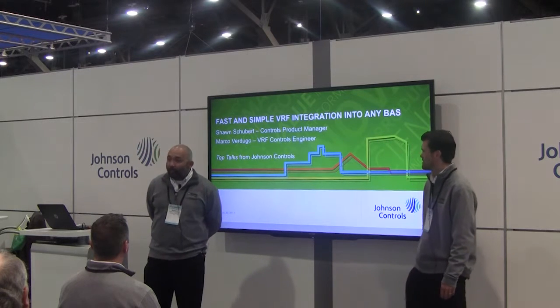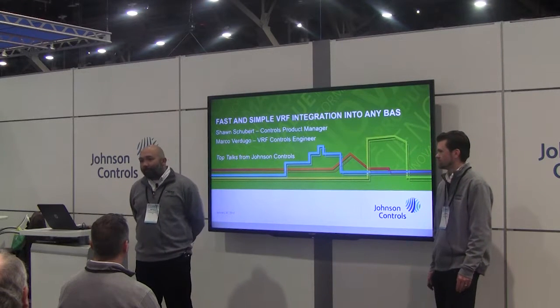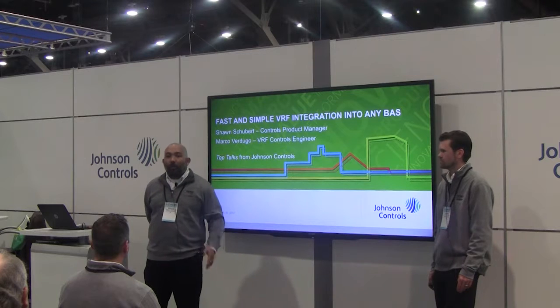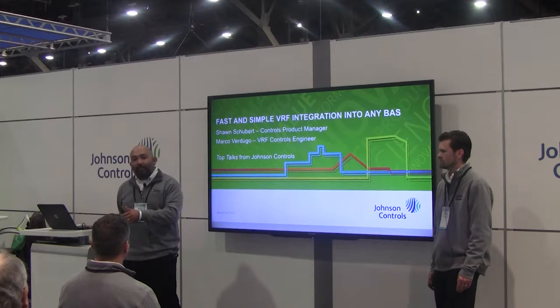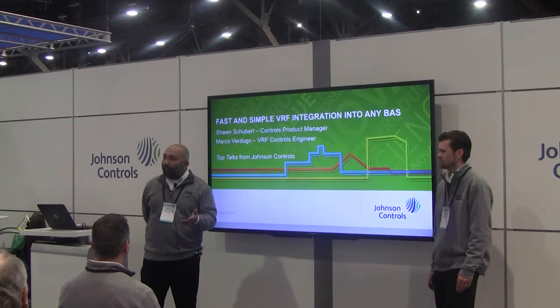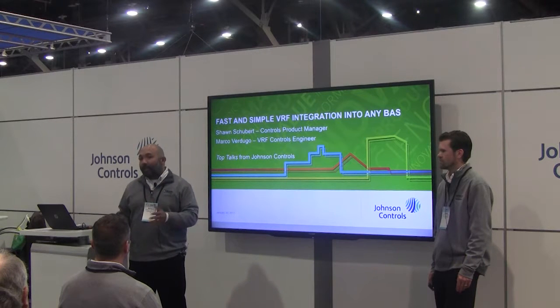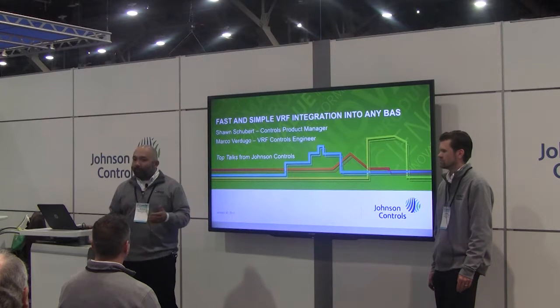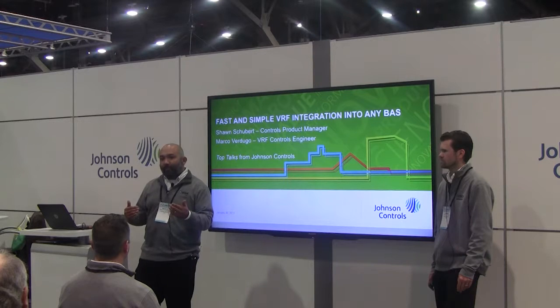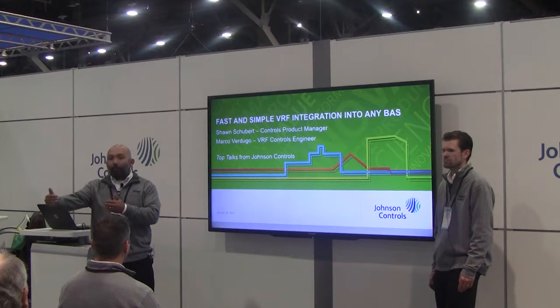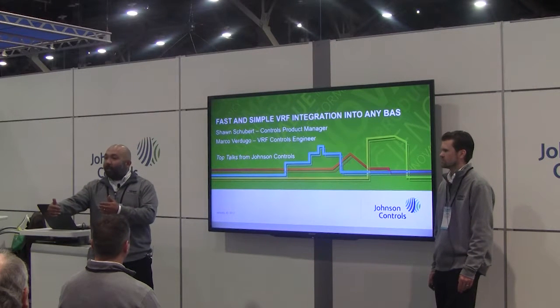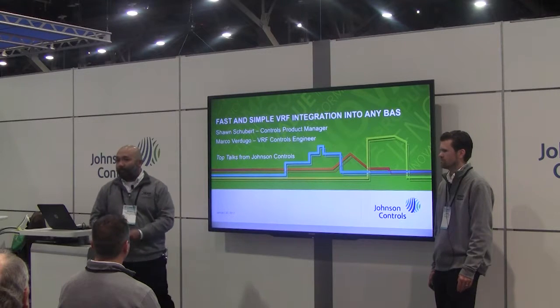Sure. So we have two types of systems. We have a heat pump system, which will either do all heat or all cooling at the same time, or a heat recovery system, which has the capabilities of cooling and heating at the same time. So it'll take a bank of units on the outside and up to 64 indoor units on the inside, and we can accomplish this heating and cooling with changeover boxes.